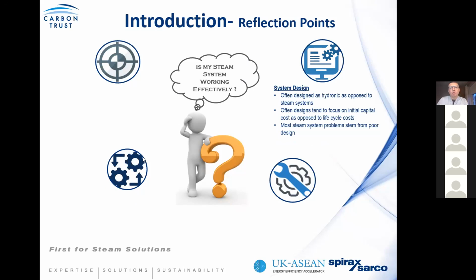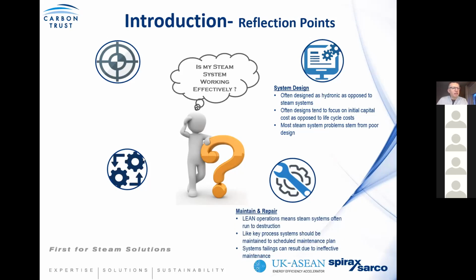From our experience, we have found that the biggest problem is the actual design of the system. We find that some engineers don't really understand what a steam system is and design it similar to a water system. And we're finding that a lot of the problems with a steam system are the actual design itself. We're also seeing that, with the cost of lean operations and reducing operating costs, some companies are put under pressure to minimize costs where possible. And we're finding that some maintenance procedures are lacking, not because of intent, but because of budget constraints. Again, minimum maintenance or lack of certain maintenance can have an impact.